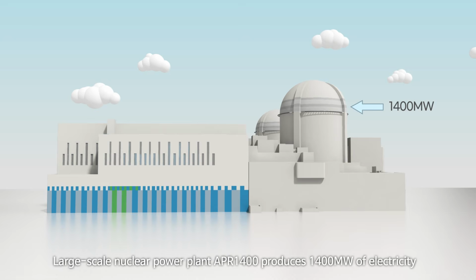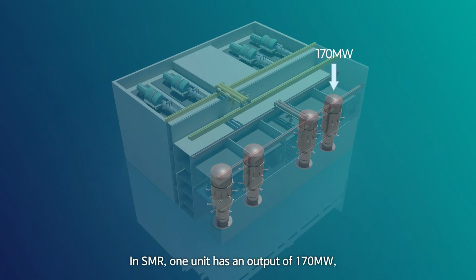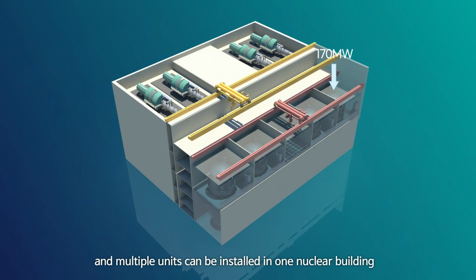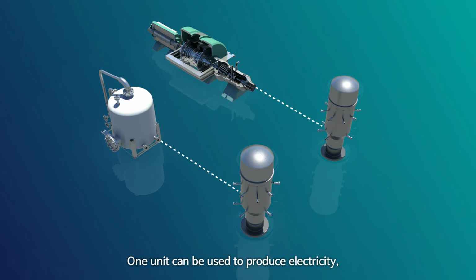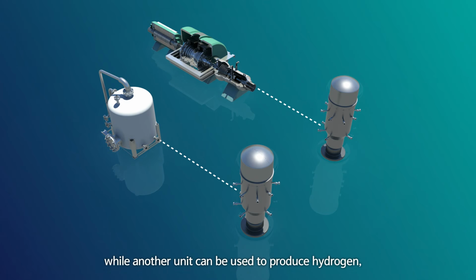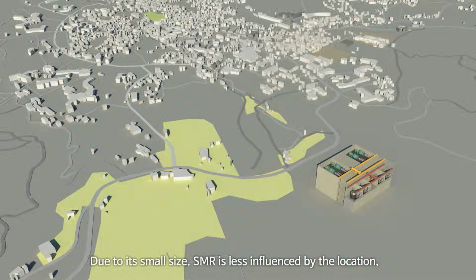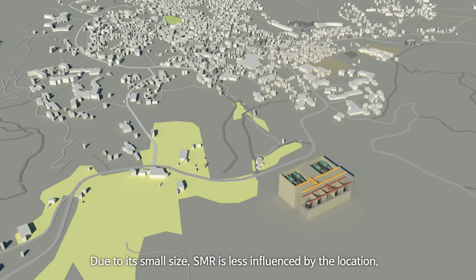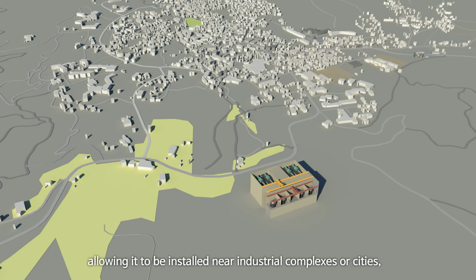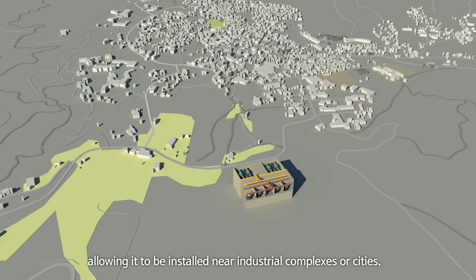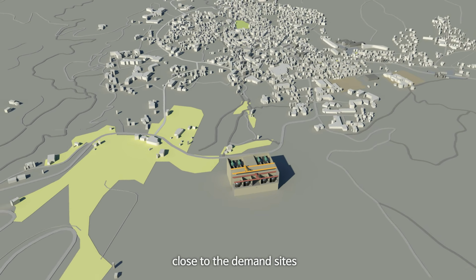Large-scale nuclear power plant APR 1400 produces 1,400 megawatts of electricity. In SMR, one unit has an output of 170 megawatts, and multiple units can be installed in one nuclear building. One unit can be used to produce electricity, while another unit can be used to produce hydrogen, ensuring flexibility in terms of its use. Due to its small size, SMR is less influenced by the location, allowing it to be installed near industrial complexes or cities close to the demand sites.